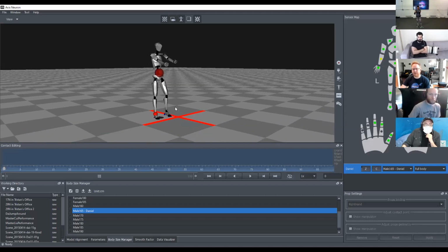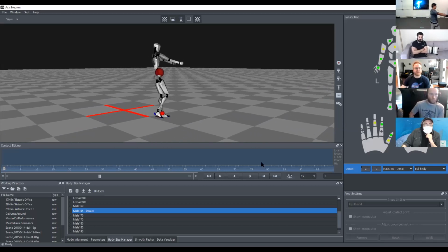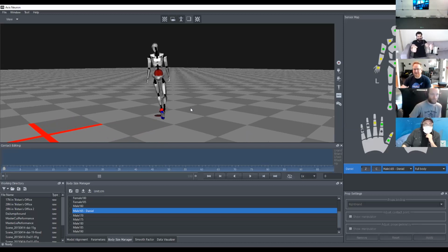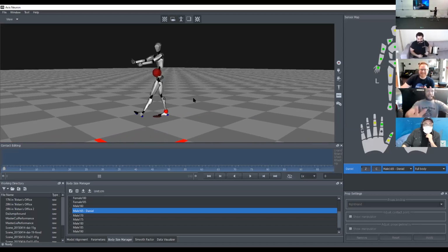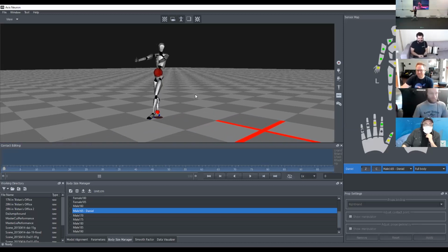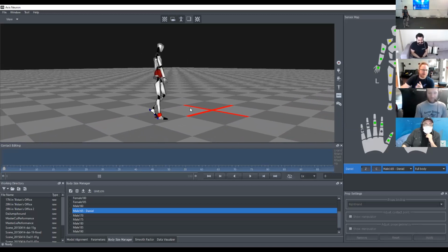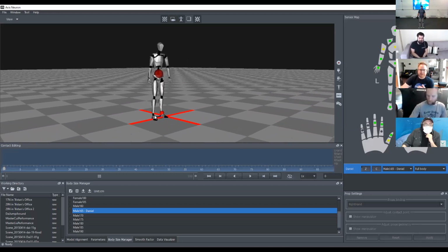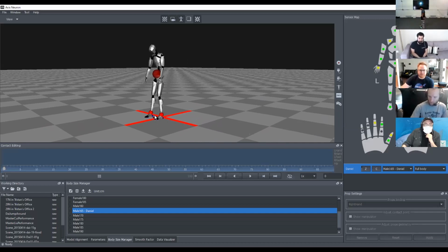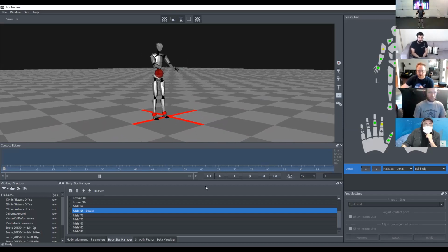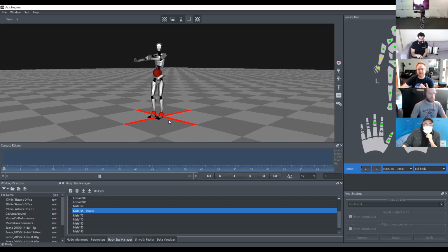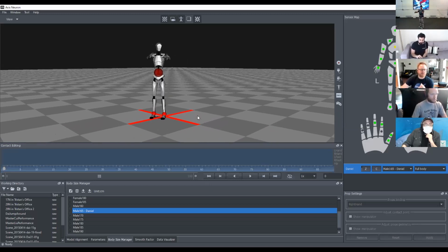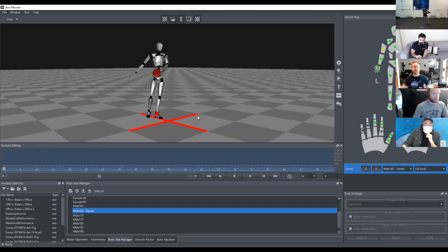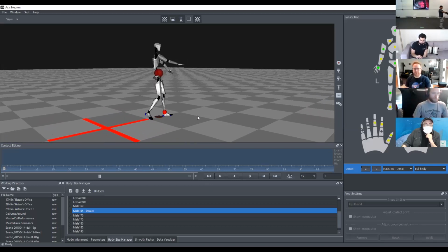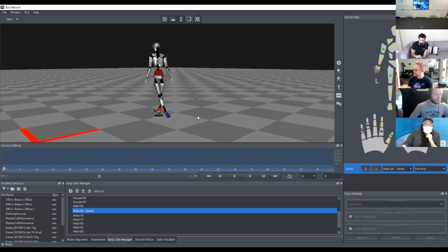And then I say, go ahead and take a quick lap for me. Walk around in a circle. You can relax your hands. He's going to walk around the whole time. Terminator position. The reason I do that right after a calibration is to make sure the sensors are giving me data that looks correct. So check the fingers and the arms, have the legs swing, and then have them take a walk in a circle so that their regular ambulatory movement is reflected properly in the skeleton.